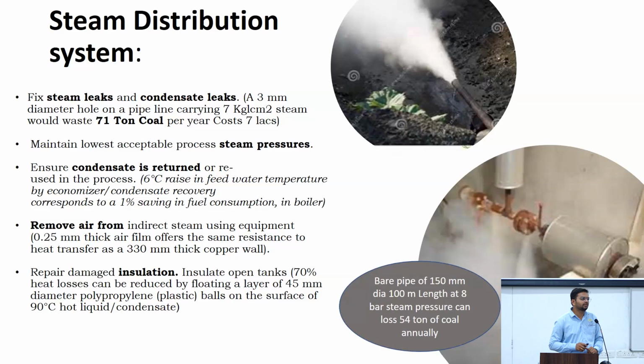and that can be the reason for efficiency loss also. As well, the steam system needs to provide air-free steam distribution, because we need to vent the air that is introduced in the steam distribution system. The air venting is necessary because air can cause expansion action and water hammering action also, and a 0.25 mm thick air layer can act as an insulator. So air is damaging; it causes a damaging action.